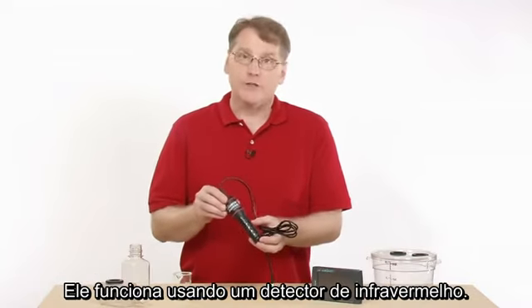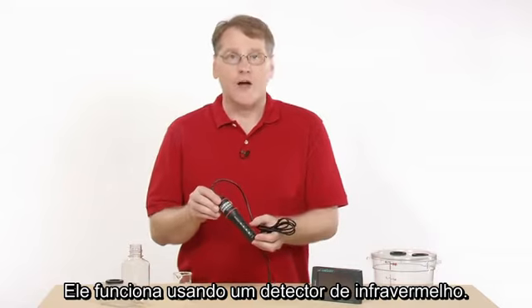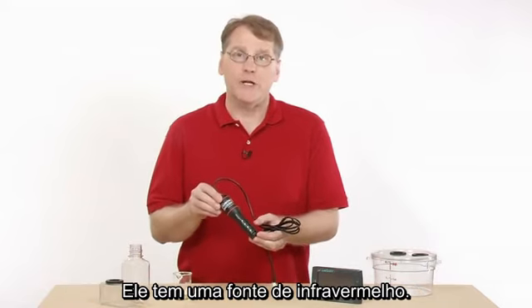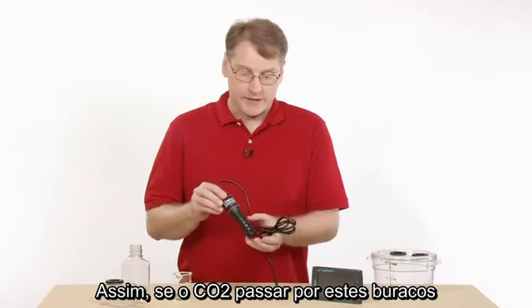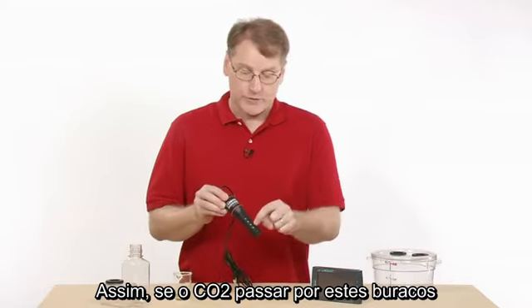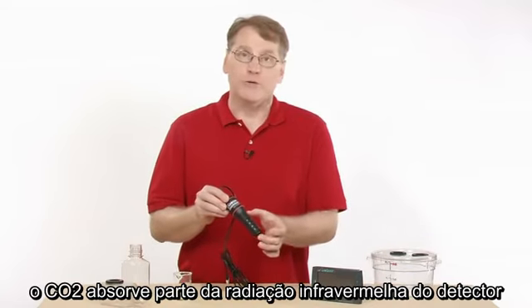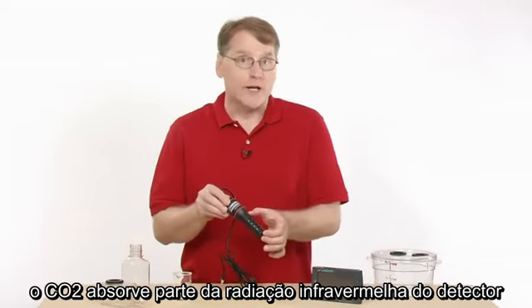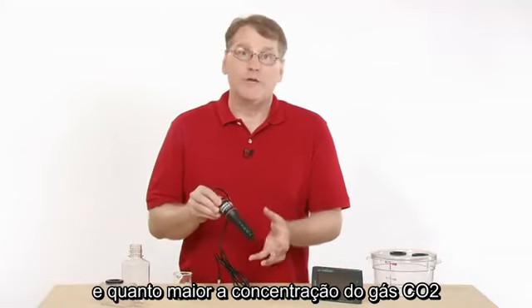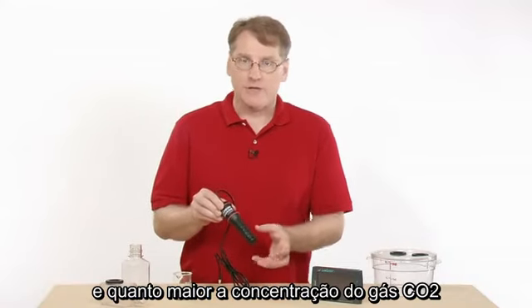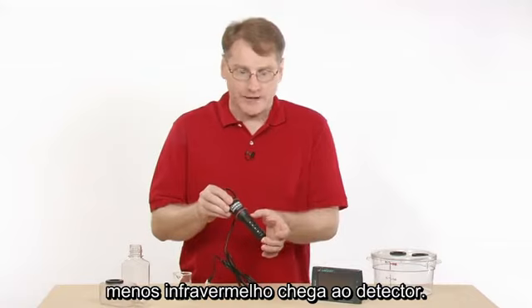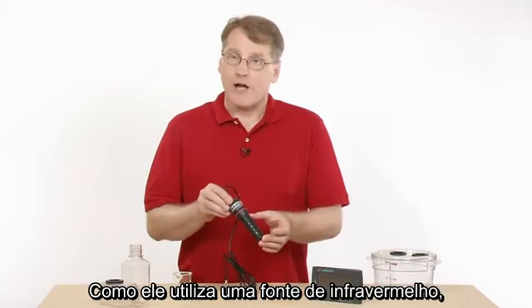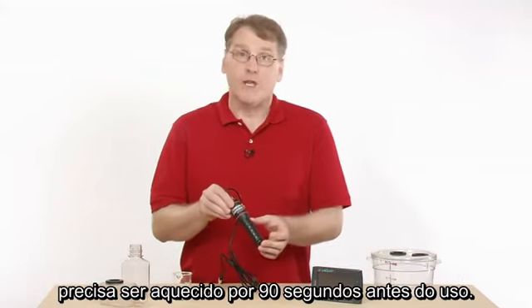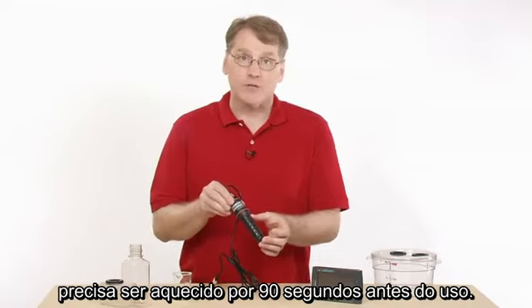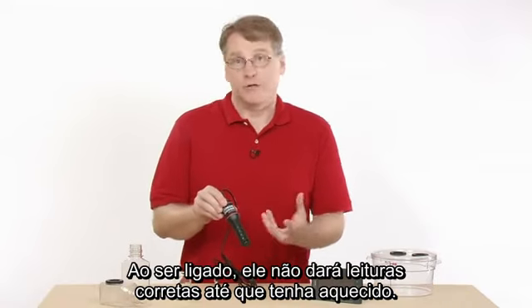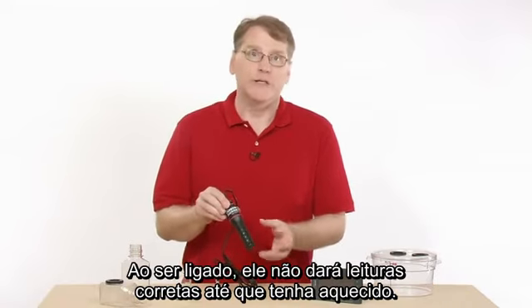And the way this sensor operates, it actually uses an IR detector. And so it has an infrared source, and if the CO2 goes through these holes, the CO2 will absorb some of the infrared radiation from the detector, and the higher the concentration of the CO2 gas, the less infrared makes it to the detector. Now, since this is using an IR source, you do need to let it warm up for 90 seconds when you use it.